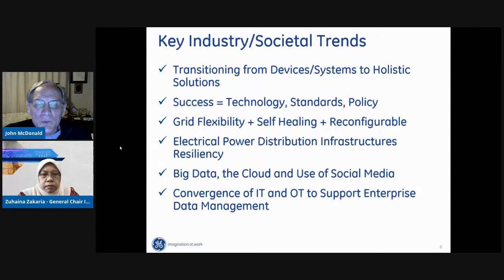What's really important today is grid flexibility or self-healing - being able to reconfigure the grid. We have logic, I'll show you a little later, that we can put on, for instance, the distribution part of the grid where we can automatically detect the fault, locate the fault, isolate the fault, and restore service upstream and downstream of the faulted segment within one to two minutes. Truly a self-healing grid with no person involved. But part of this is a cultural change - one thing is the technology, and the other is convincing the customer, convincing the people at the customer, the engineers, to accept this new technology, have confidence in the logic, and be able to close the loop, taking the people out of the loop and letting it self-heal.